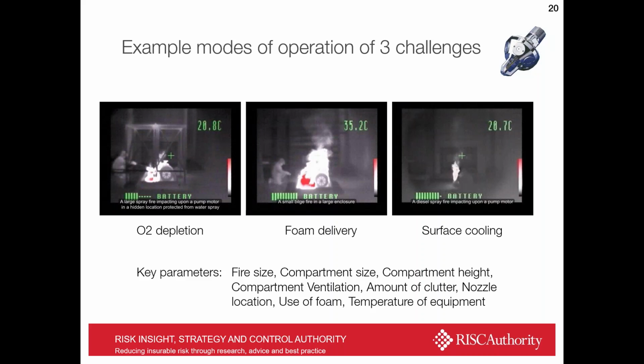The surprising thing about this is this fire isn't actually tackled by oxygen depletion. It's too heavily ventilated for that. It's a small fire, it doesn't generate much steam, but in this particular case, the fire only goes out because the object on which the diesel fuel impacts is brought down below the auto ignition temperature of the fuel. So it's actually about surface cooling and removal of the ignition source.